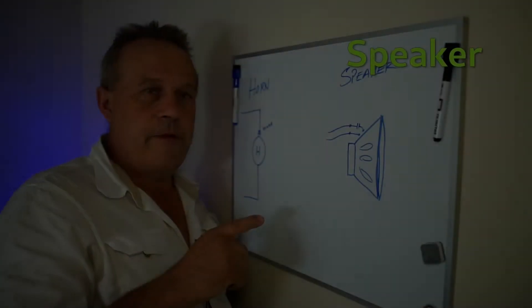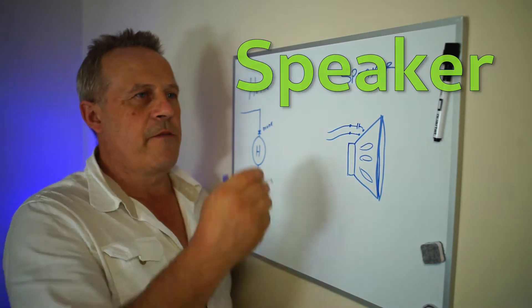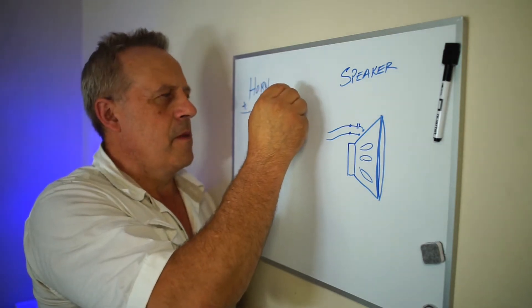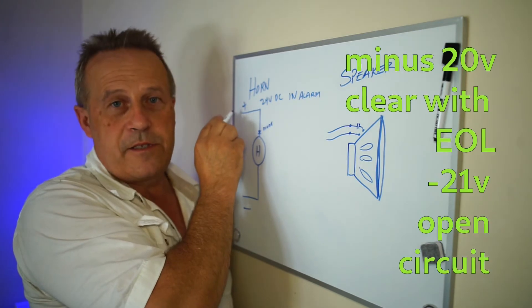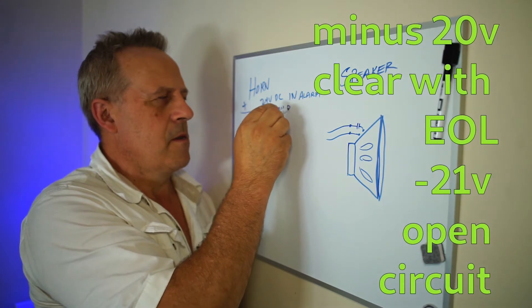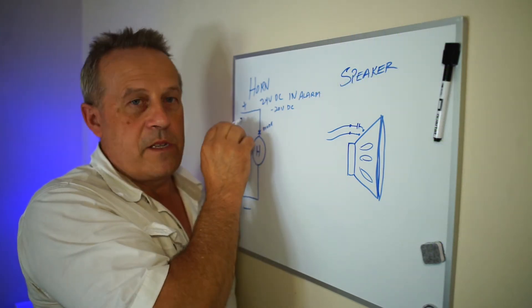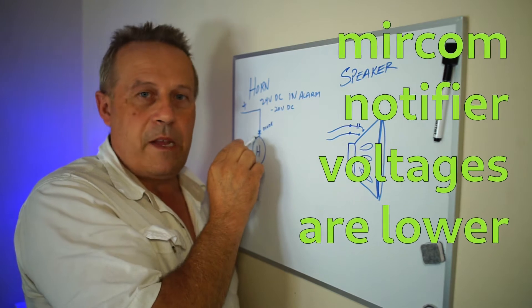The difference between a horn and a speaker: a horn is 24 volts DC. When it's in alarm, the positive is present. When it's not an alarm, this becomes minus — about minus 20 volts. There's a blocking diode that only activates when it's an alarm. That's why you don't hear the horns when it's not an alarm, because that is a minus — the blocking diode stops it. Sometimes you can see that blocking diode on the meter.